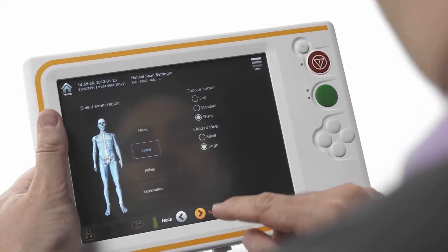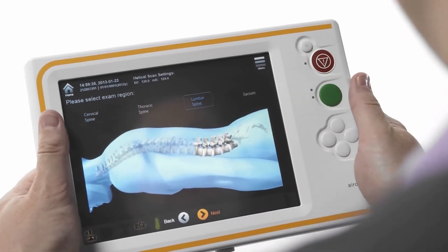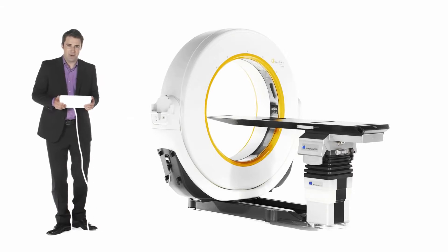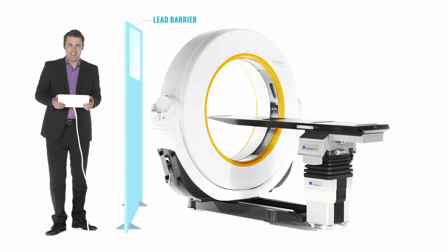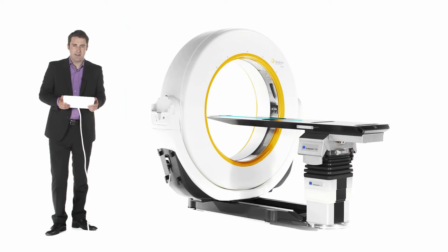After an initial low-dose scout scan, a 3D scan range can be defined. The 32-slice detector array of Airo provides a detailed anatomical context for clinical decision-making. Acquired in helical mode with 1mm slice thickness, the scan volume can be set to a maximum of 100cm in length and 50cm in diameter. This range allows surgeons to image the entire spine in a single scan in about 30 seconds.